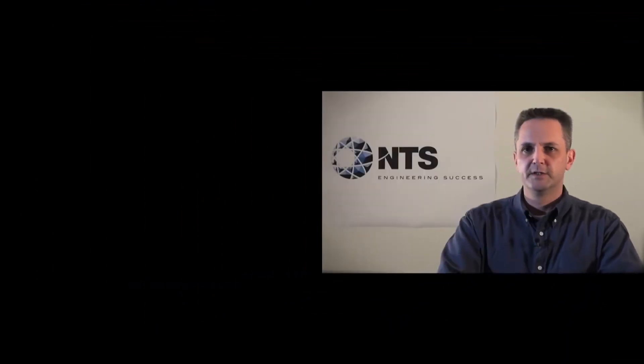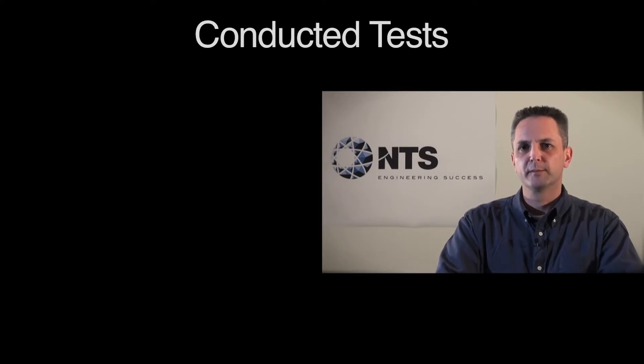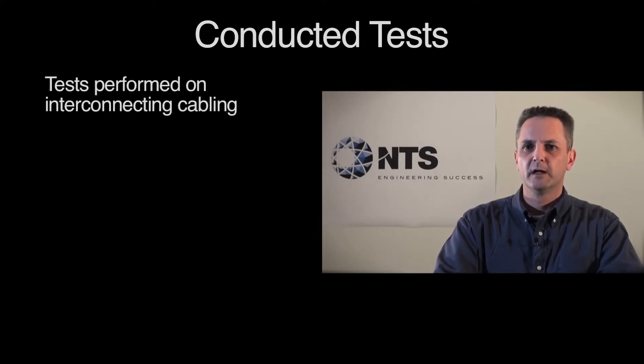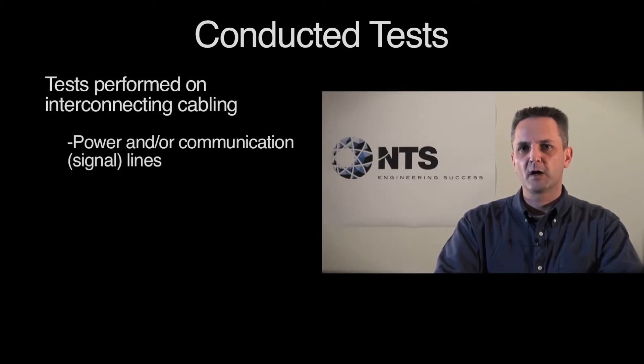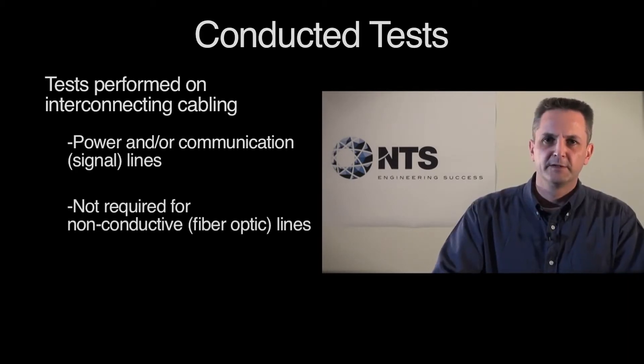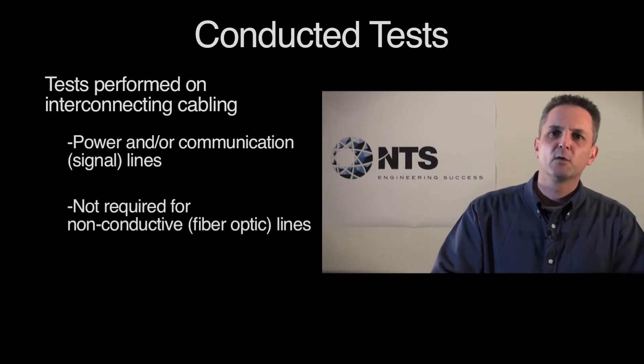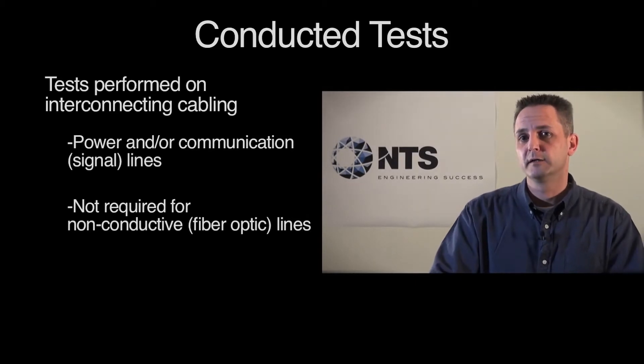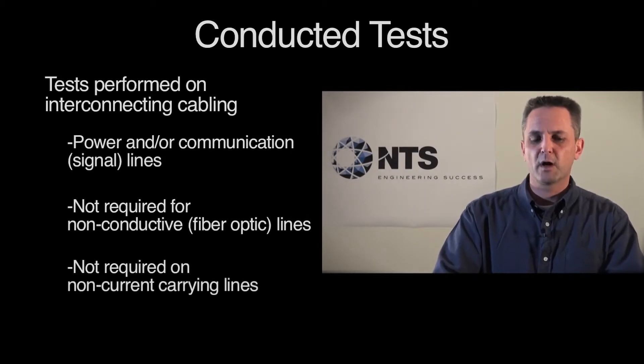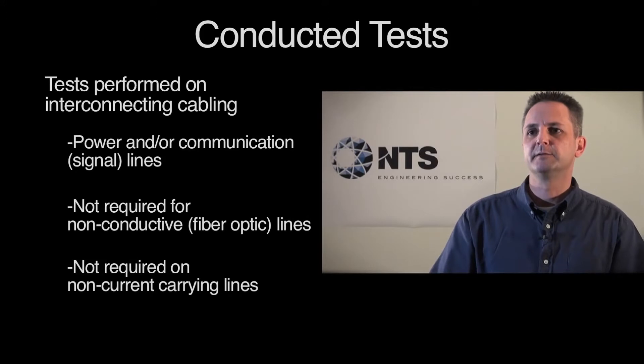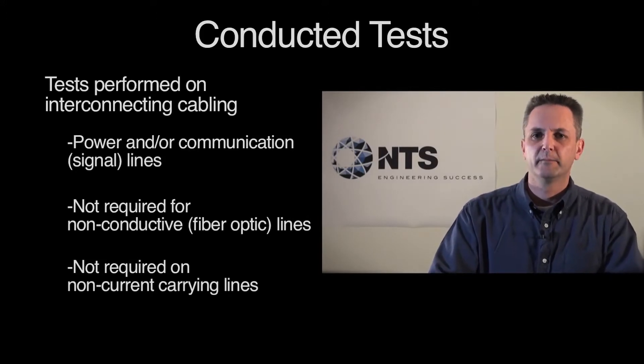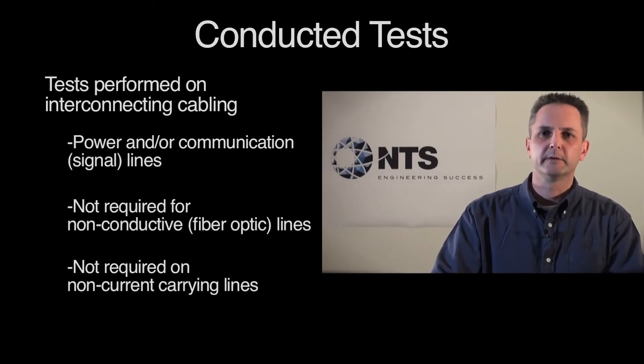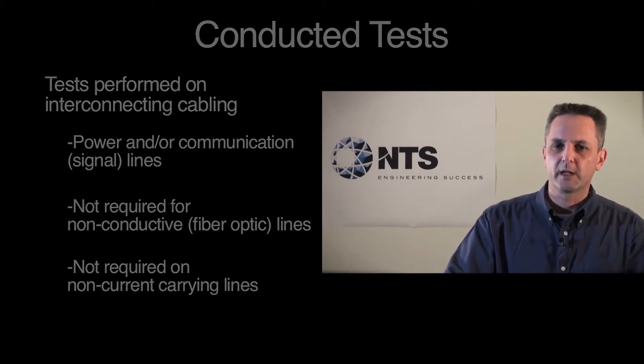Within these two types of tests — emissions and susceptibility tests — there are two classifications. One would be conducted tests, which are primarily performed on interconnecting cabling, such as communication lines and power lines. Testing for conducted emissions or immunity is not required on fiber optic lines, non-conductive lines, and is not required on non-current carrying lines, such as metallic hoses or hydraulic lines, or even grounding straps in most cases.